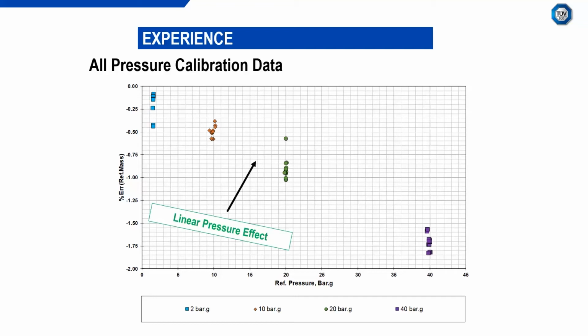So that's how we operate at NEL with the elevated pressure and temperature facility. Say a customer is operating at 20 bar. We might then perform a calibration at 20 bar, but we'd also do some additional points at 25 or 30 bar, and also say 10 or 15 bar gauge. That will give us a couple of pressures, and we can derive a linear pressure correction. We can then complete some additional points again at 20 bar to ensure that this pressure correction is robust. It's fully traceable, and we know the overall uncertainty of this correction. So that's a good thing about Coriolis meters: although they appear to be affected by pressure, it's linear. Linear is good news because it's easily corrected.